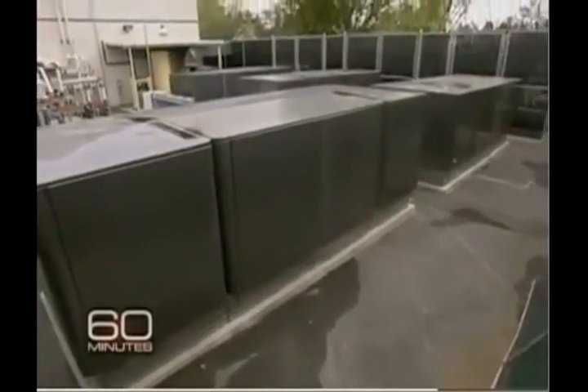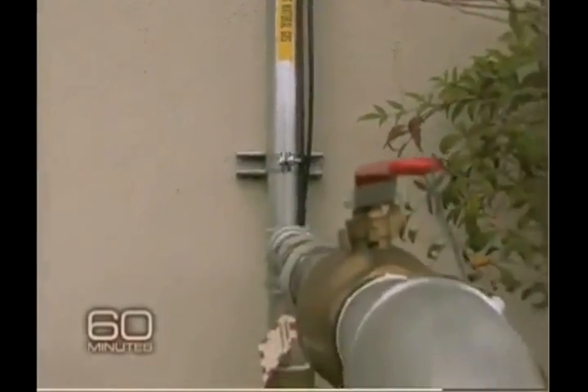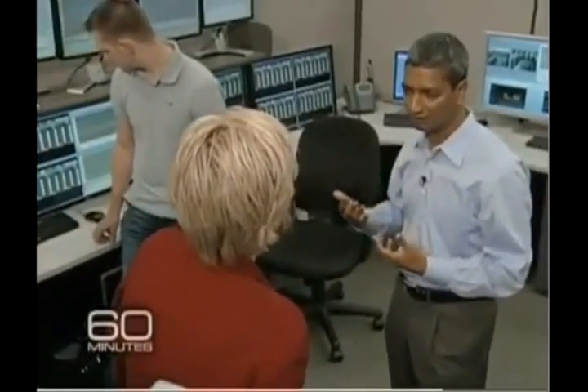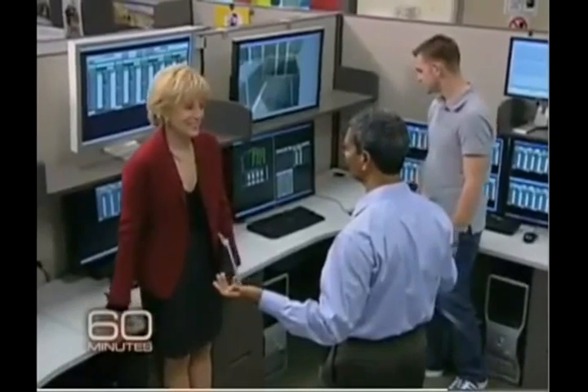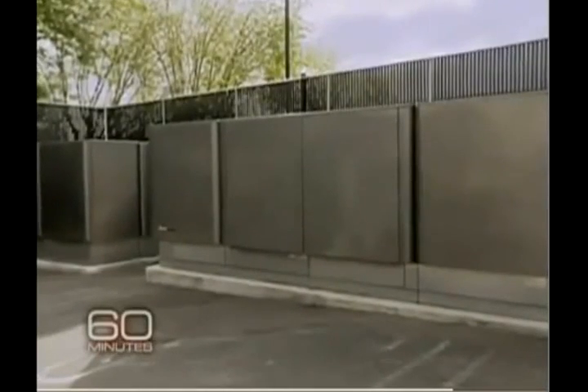These four units have been powering a Google data center for 18 months. They use natural gas, but half as much as would be required for a traditional power plant. K.R. told us that three weeks in at Google, suddenly one of the boxes just stopped — your heart just drops. Did you panic? For a short while, yes. He fixed that, then there was another incident: the air filters clogged up, air wasn't coming into the system because the highway was kicking up dirt. He flipped the system around and the problem was gone.